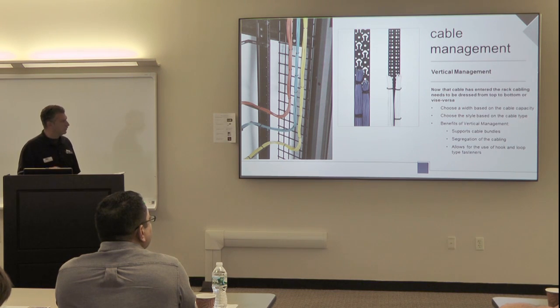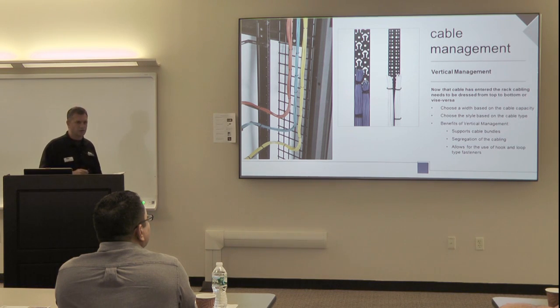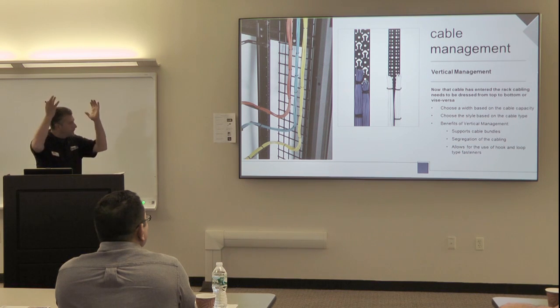So again, choose a style based on the cable you're using. If you've got a lot of power cords, you could do something like this. Wire ties aren't going to hurt your power cords as much as they'd hurt a category cable. The benefits are supporting the cables, pull force, bend radiuses, and things like that, plus the cable segregation we talked about, as well as allowing for the hook and loop fastener. So now I've got my rack all vertically dressed.